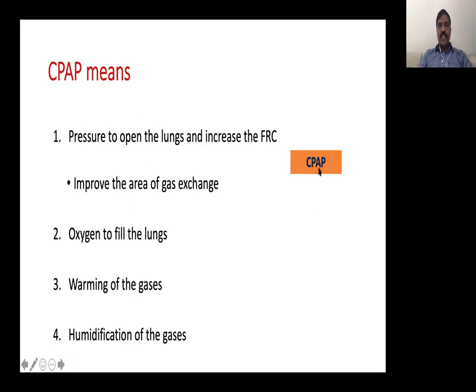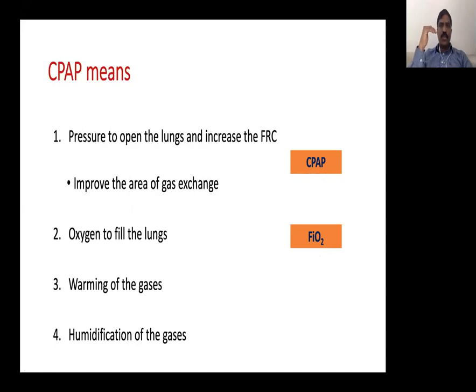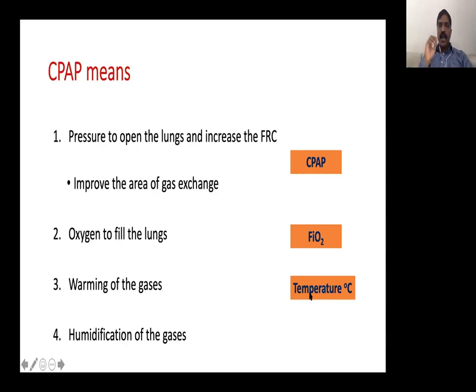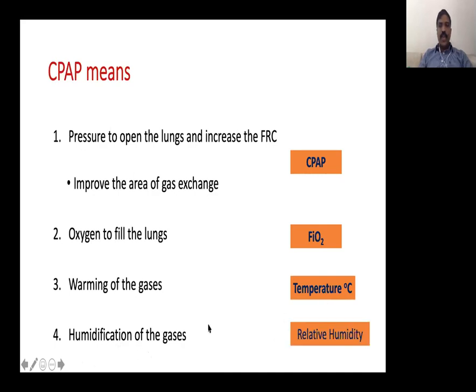CPAP pressure is measured in centimeters of water. Oxygen is measured as fraction of inspired oxygen (FiO2) — room air is 21% and we target a maximum of 60%. Warming is measured in temperature; gases should reach the baby at body temperature, 37°C. Relative humidity is how we measure humidification; we want 100% relative humidity when gas reaches the nostrils.